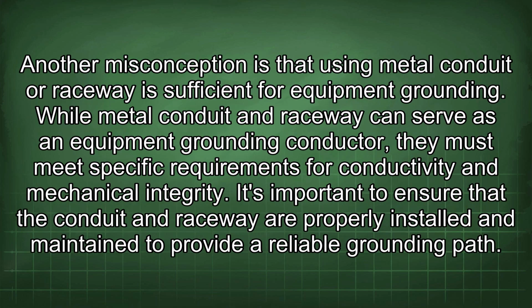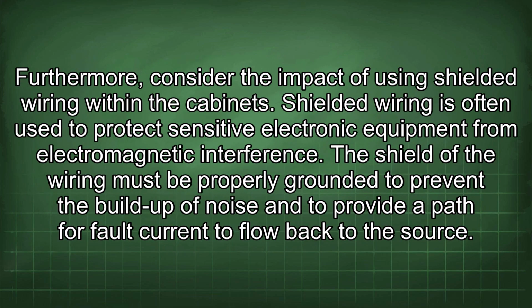Another misconception is that using metal conduit or raceway is sufficient for equipment grounding. While metal conduit and raceway can serve as an equipment grounding conductor, they must meet specific requirements for conductivity and mechanical integrity. It's important to ensure that the conduit and raceway are properly installed and maintained to provide a reliable grounding path. Furthermore, consider the impact of using shielded wiring within the cabinets.